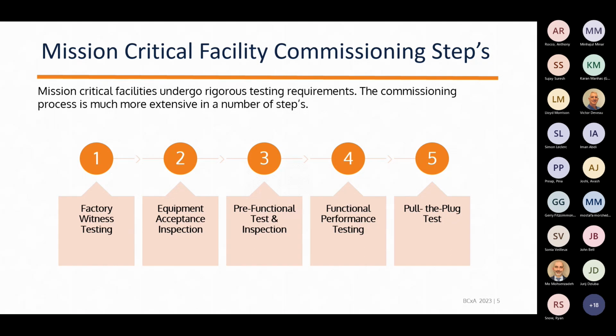Step 2 is acceptance. When equipment comes to site, we want to make sure it hasn't been damaged, it's in good shape, and all the parts are there to get it installed. I've had equipment show up without parts, damaged. A good example is a cooling tower that showed up hit by a tree. There was no structural damage, so we got a great rebate and I asked them to extend the warranty on the tower. It was a win-win for us all.